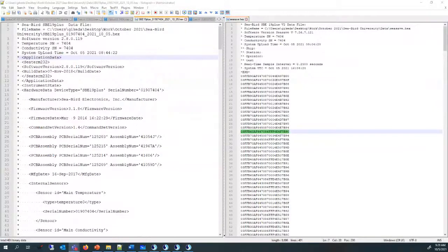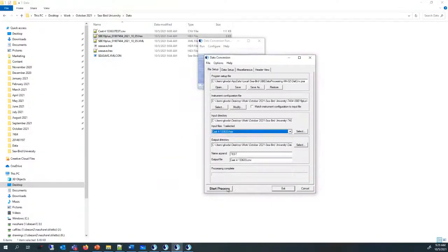All right, next one. Sometimes when I select my con file as well as the corresponding hex file and press start process, nothing happens, and it says processing stop. So what this problem means, and I think Greg kind of touched on this a little bit, is that you actually have to make your con file match what's being sent out by the instrument itself in the hex file. We call this a scan length error. This means that your con file doesn't match the data that's actually being produced by your instrument, and the software is expecting a certain amount of hexadecimal lines and characters, and it's getting less of them.